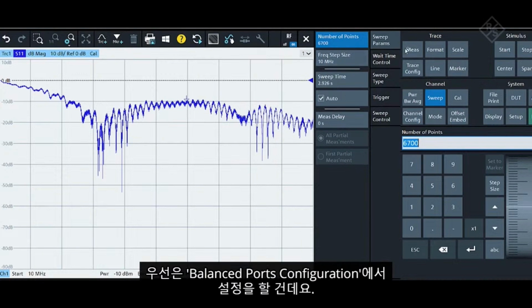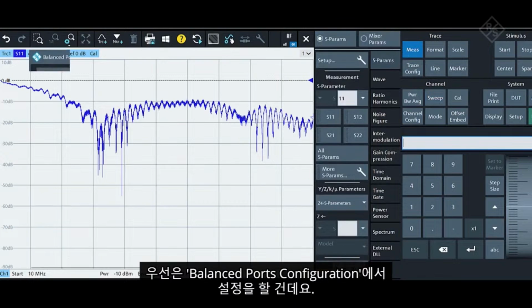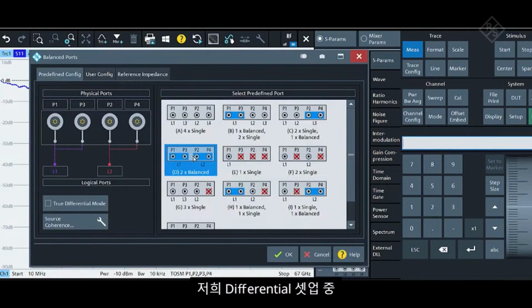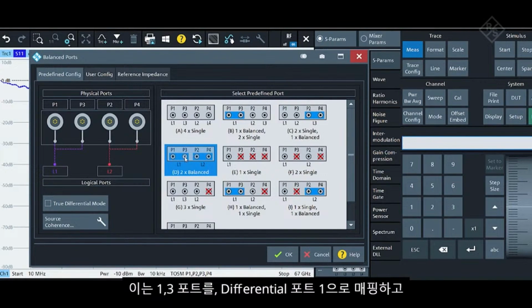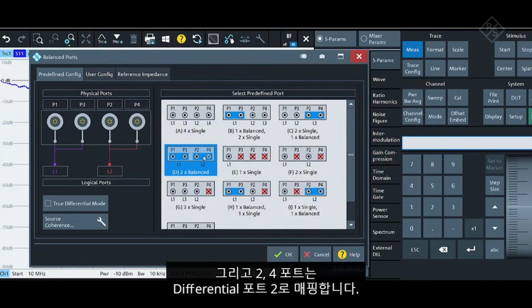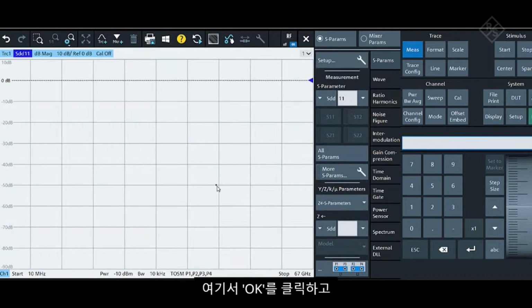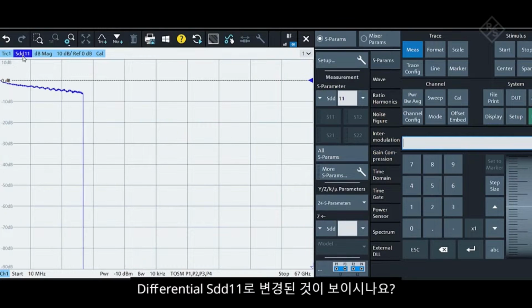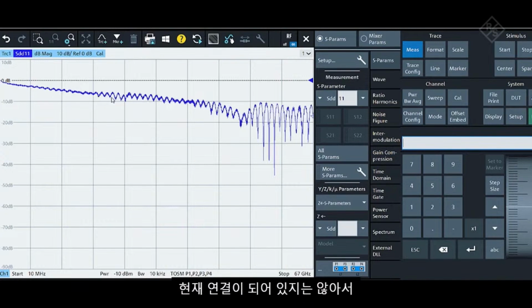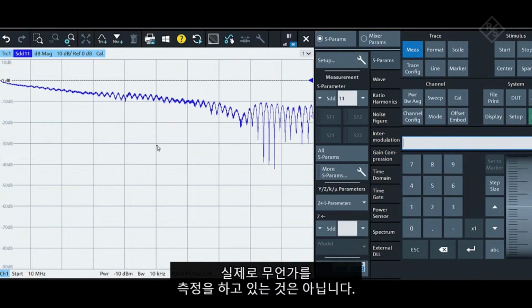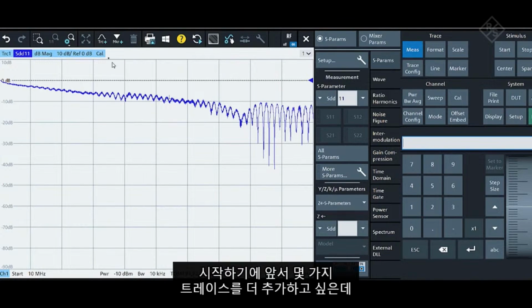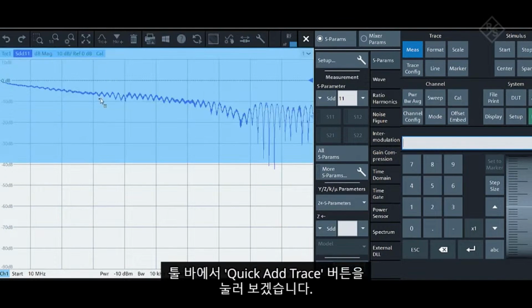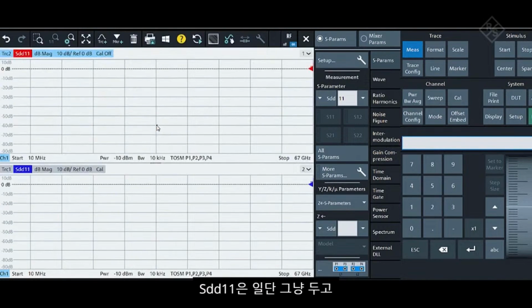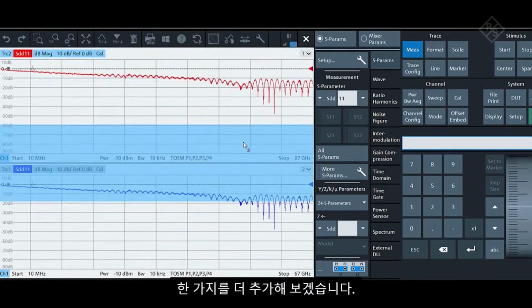First thing is I want to set in our balanced port configuration our differential setup. We have a predefined selection which maps ports 1 and 3 to differential port 1 and ports 2 and 4 to differential port 2. I'll say OK. Notice we now went from single-ended S11 to differential SDD11. I'm not really connected to anything now, so we're not really measuring anything at the moment. I want to add a couple more traces before we get started. So I'm going to take my quick add trace button from the toolbar. SDD11 is fine for now. I'll do one more.